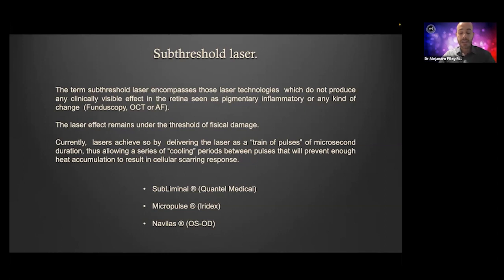Currently, all the lasers that qualify for subthreshold achieve this by delivering the laser not as a continuous pulse, but as a train of very short bursts separated by cooling periods — periods during which there is no laser energy delivery — which prevents the accumulation of critical heat that would result in burning, coagulation, and visible scars.